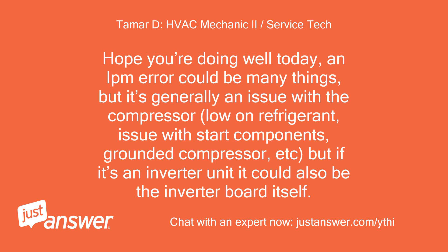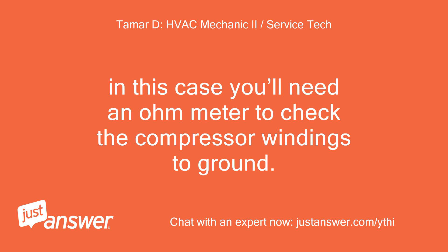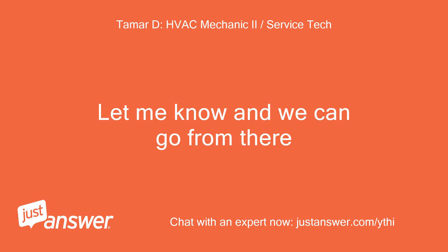An IPM error could be many things, but it's generally an issue with the compressor, low on refrigerant, issue with start components, grounded compressor, etc. But if it's an inverter unit it could also be the inverter board itself. In this case you'll need an ohm meter to check the compressor windings to ground. Let me know and we can go from there.